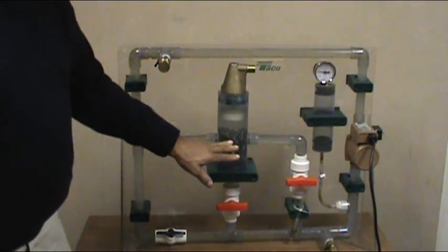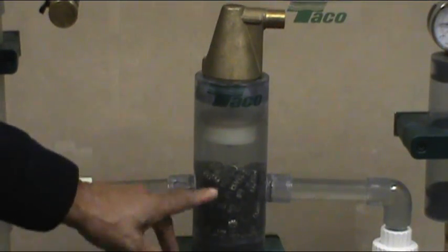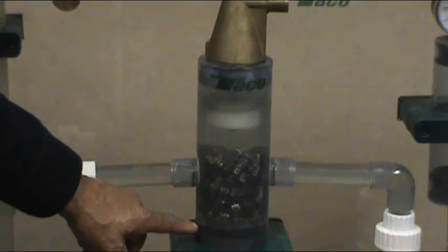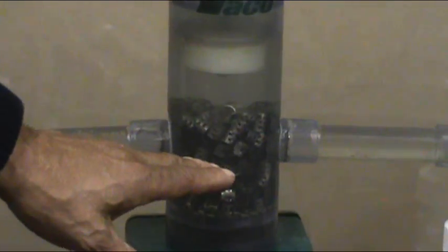Let's see what happens when we add a good quality air eliminator to our system. We're going to divert that flow from just circulating around and around through this model of the Taco 4900 air eliminator. In the bottom of the barrel, you see the stainless steel pall rings that the air entrained water must go through to separate out.